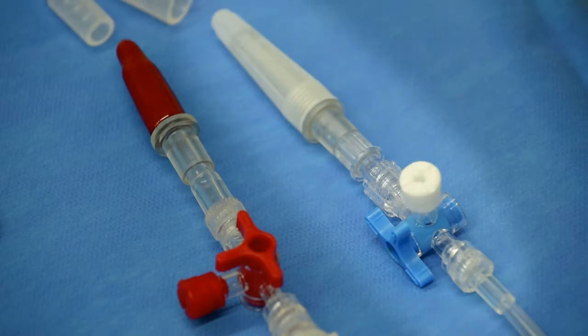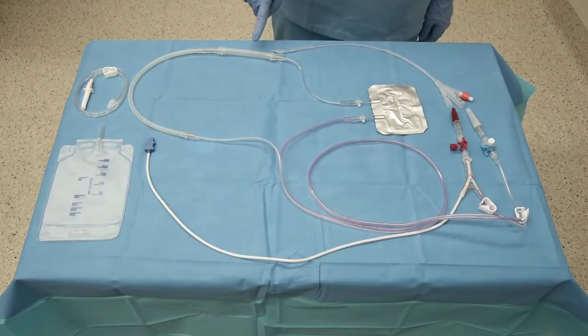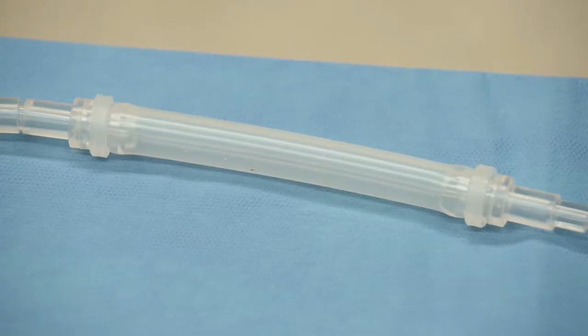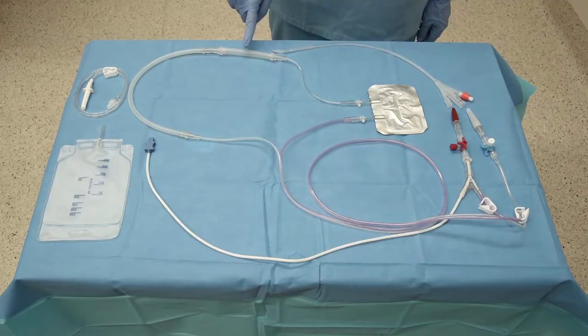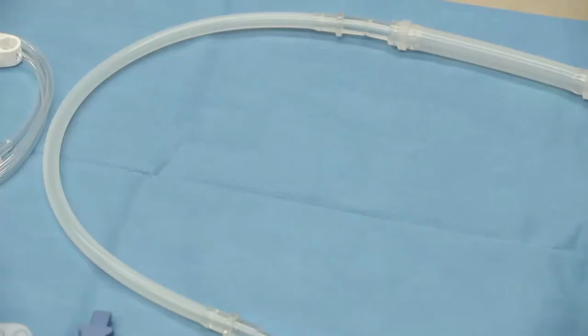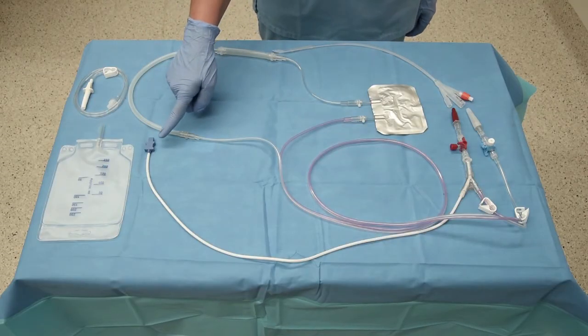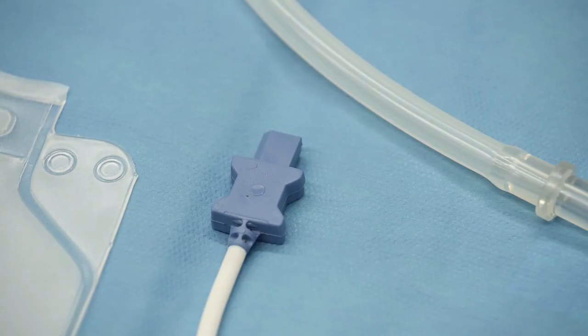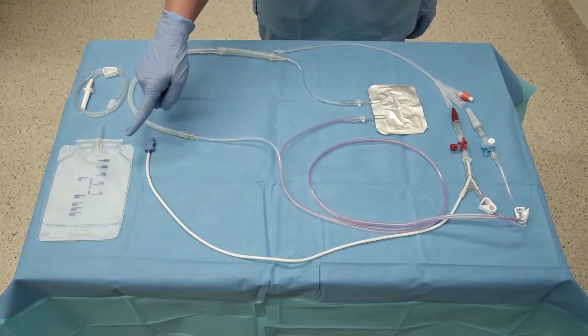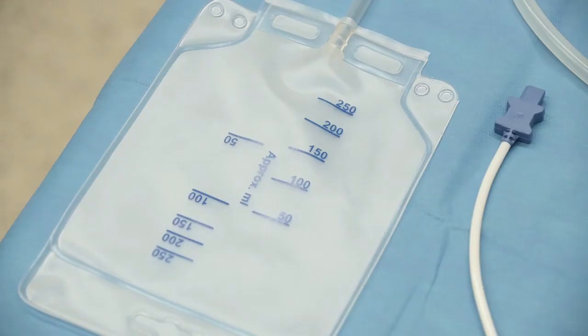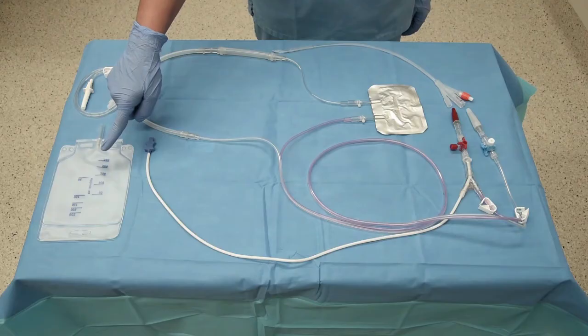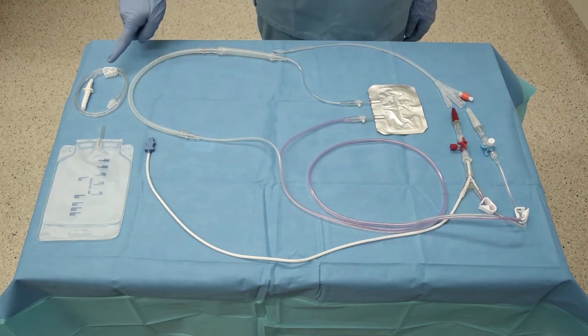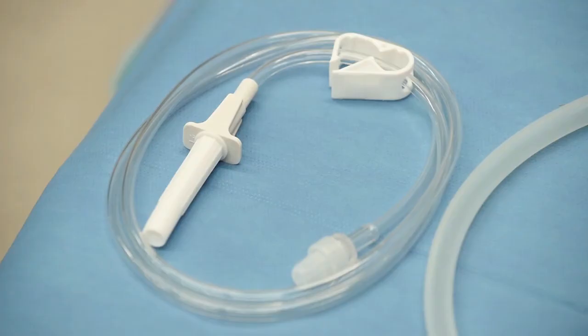to the large aspiration port of the catheter, a short, stout pressure-sensing silicone tubing that will be inserted into the pressure sensor housing, a long, thin silicone tubing that will be placed into the peristaltic pump, an inline temperature sensor that will be connected to the unit and continuously monitors the temperature of the liquid within the disposable set. The disposable set also comes with a waste drainage bag for safe disposal of fluids at the end of the treatment, alongside a waste drainage line to allow the connection of the bag to the giving set.